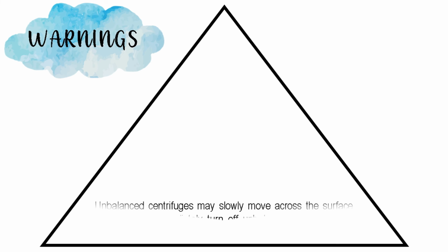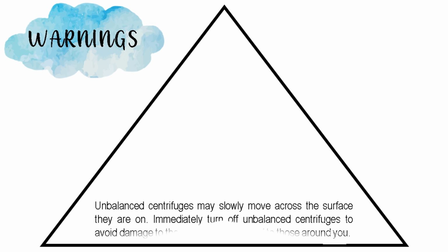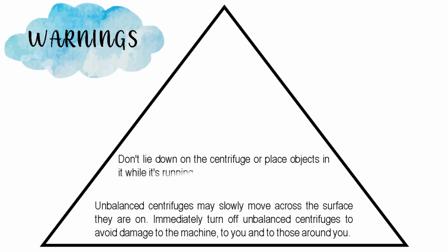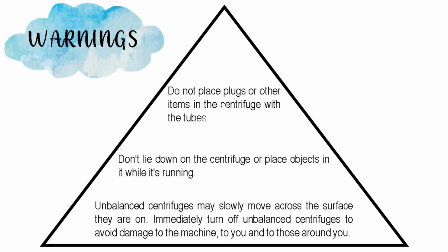Always wear gloves. Warnings: an unbalanced centrifuge may slowly move across the surface. Immediately turn off an unbalanced centrifuge to avoid damage to the machine, to you and to the people around you. Don't lean on the centrifuge or place objects on it while it's running. Do not place plugs or other items in the centrifuge with the tube.